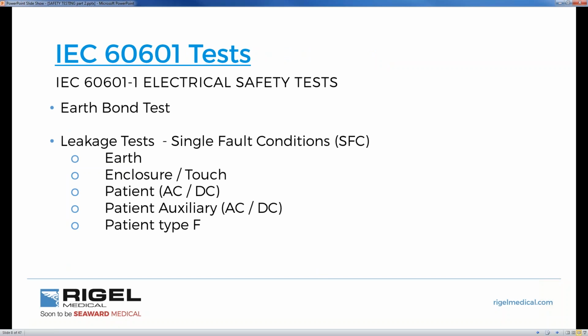So what tests do we do as part of an electrical safety test for 60601? We do an earth bond test, and we do leakage tests under various single fault conditions. We do earth leakage, we do enclosure or touch leakage as it's otherwise known. We do patient leakage, measuring AC and DC currents. We measure patient auxiliary AC and DC leakage, and we measure patient F-type.